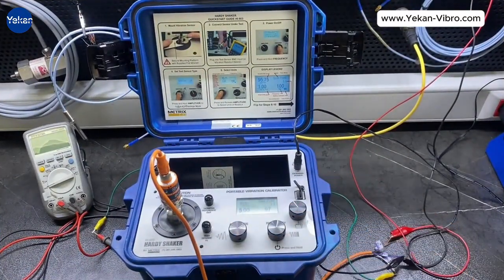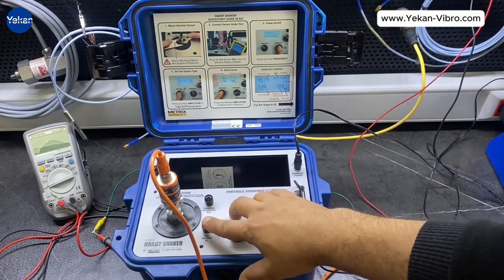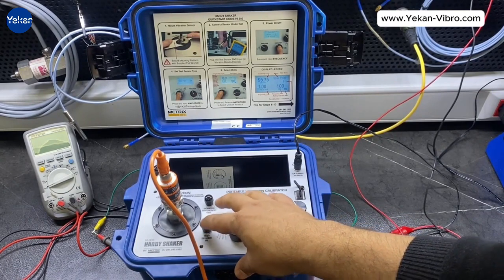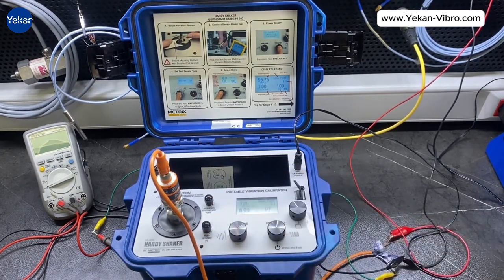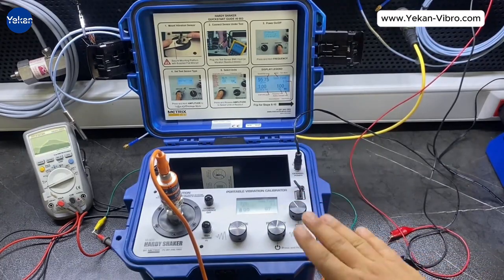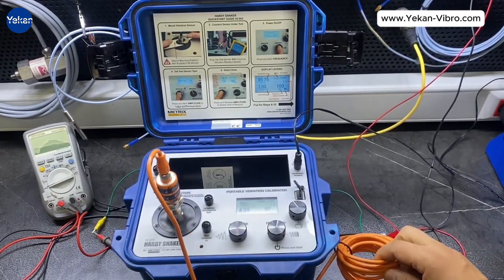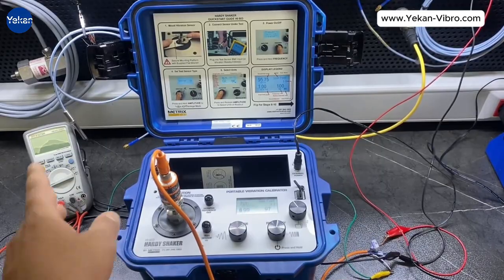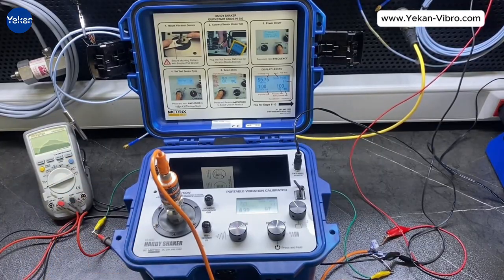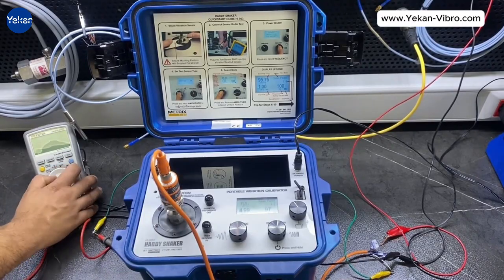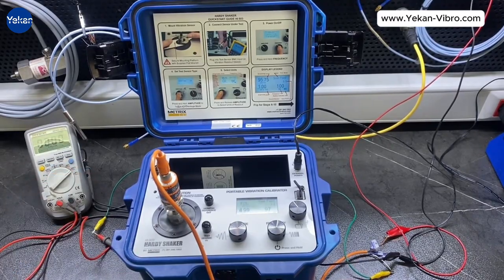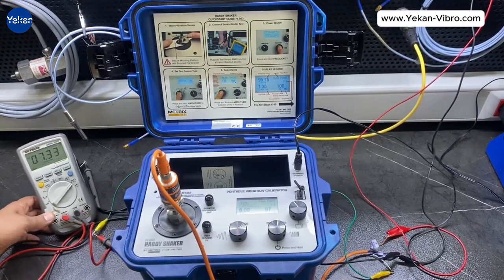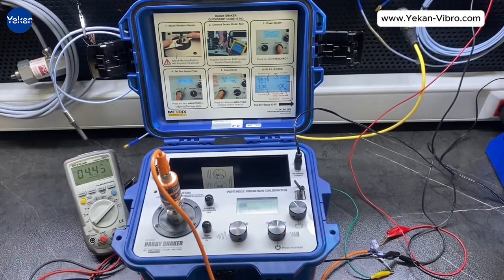Now we move to the device. We mounted the IFM sensor onto a Metrix shaker. This shaker has one input for millivolt sensors. It displays sensitivity error on the screen. But it does not support 4 to 20 milliamp sensors, so we connected the sensor output directly to a multimeter to read the current. I am now powering the sensor and securing the shaker. As seen on screen, the multimeter shows 4 milliamps, which means no vibration is present. This matches the expected base value of a 4 to 20 milliamp sensor.